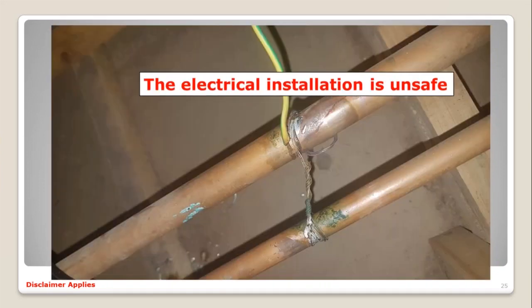Okay, there is one of the examples that we just talked about. If I need to remove that pipe now, I need to cut away all the wire and desolder it. That will be such additional work, where you could have just made a proper bonding strap around it and put a crimping on it. That makes it easily replaceable, or loosening it and replacing the pipes. But again, if you don't have the equipment to test that resistance, we would rather deem it as unsafe. You need to get somebody to verify that. Next slide.